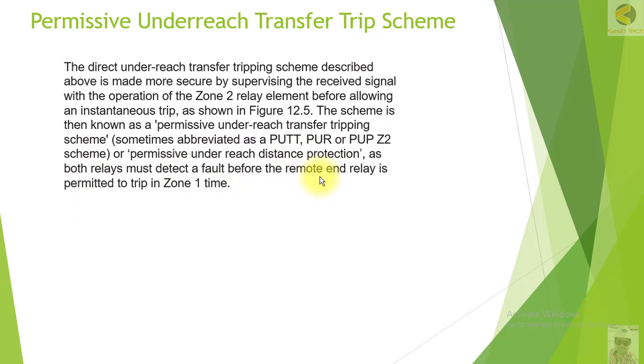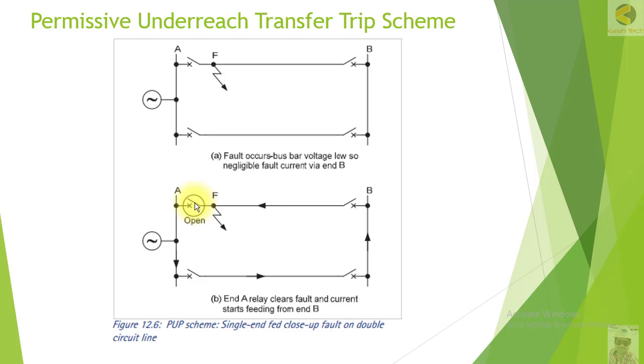In the PUTT scheme, both relays must detect a fault before the remote end relay is permitted to trip in Zone 1 time. For example, a fault occurs, busbar voltage is low, so there is negligible fault current via station B. This is one example of the permissive scheme.